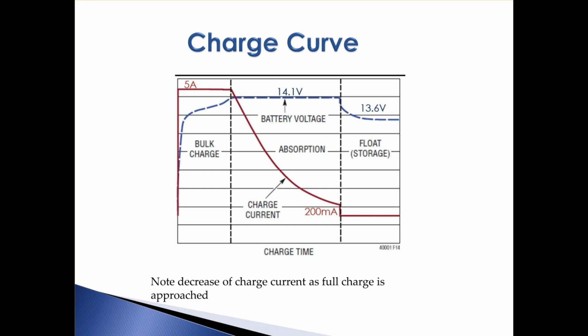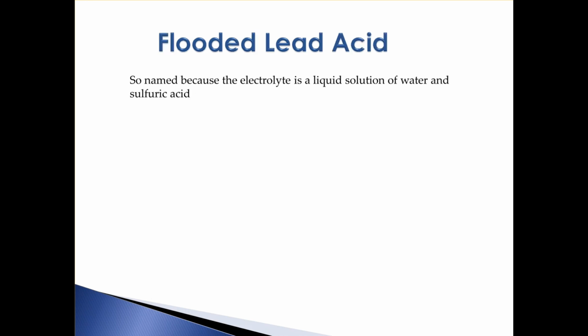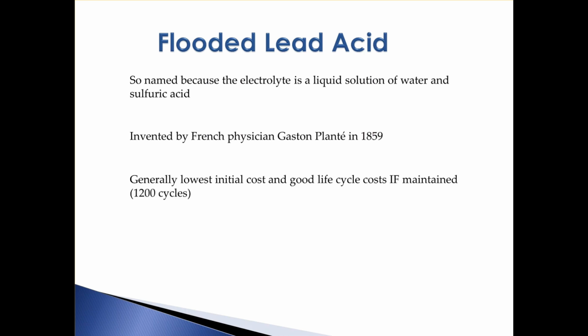Flooded lead-acid batteries, in detail, are named that way because the electrolyte is a liquid solution of water and sulfuric acid. They were invented back in 1859 by a French physician. There were other technologies around at that point that had made batteries, but he's the one that came up with the current system of lead and sulfuric acid being the battery combination. It's currently the lowest initial cost, and it has good life cycle costs if you maintain them and if you get a decent quality battery to start with.